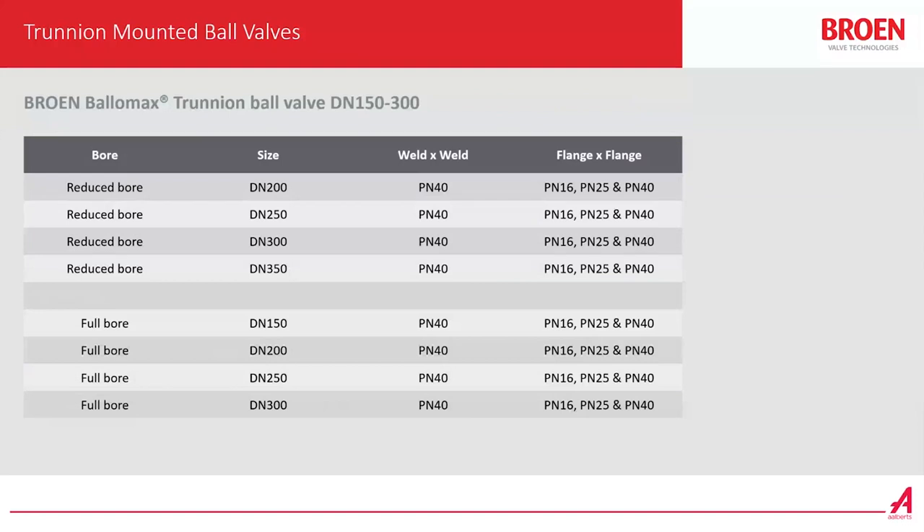The range for the reduced bore is DN200 up to DN350, and as I said, with the welding ends we have the PN40 model and for the flanged models we have PN16, PN25 and PN40. We also have four models for the full bore. The range is DN150 up to DN300 with the same pressure range: PN40 for welded ends and PN16, PN25 and PN40 for flanged.